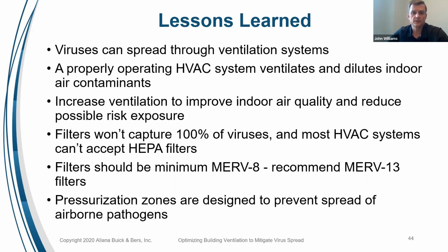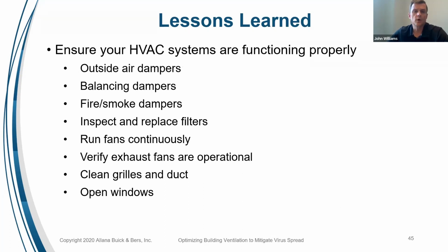We want to improve our ventilation, even though ventilation may not guarantee filtration. We want to improve our filtration. It may not guarantee we're capturing the COVID, and it may reduce our airflow, but we still want to improve that. And we recommend a minimum of a MERV 8 and no more than a MERV 13, typically. Lastly, understand and verify your pressurization zones. Know where you should be negative and where you should be positive. And go around and check your HVAC systems and check your dampers, check your filters, check if your fans are running, and look for those exhaust fans and grills, and open your windows when you can.